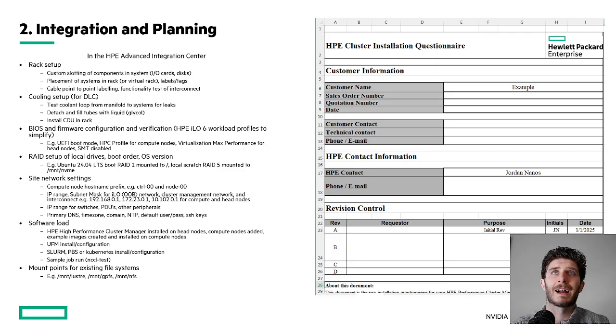When it comes to delivering racks onto the floor, there's a big consideration for integration and planning at the individual node level. If you partner with HPE, we have the Advanced Integration Center where we do this work in the factory so you do less setup when rolling racks on site and lighting them up. We set up the racks by custom slotting components and placing systems in the racks. We even label cables point to point and test the functionality of the interconnect, so we know all these components are working in the factory before shipping.